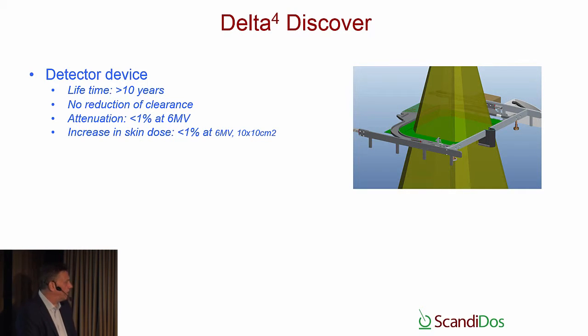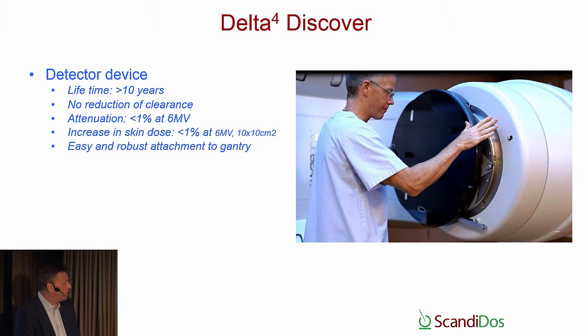Another thing that is extremely important is that it doesn't increase the skin dose. It's less than 1% at the 10 by 10 field at 6 MV. It increases a bit with bigger field sizes. That's extremely important, that it doesn't increase the skin dose too much, because the skin dose is of course something that can prevent you from delivering the treatment the way you want to deliver it. It also has a robust and easy way of attaching the device. We're using the same way to attach this device as Varian or Elekta is using to attach their accessory holders. So it's very, very robust.